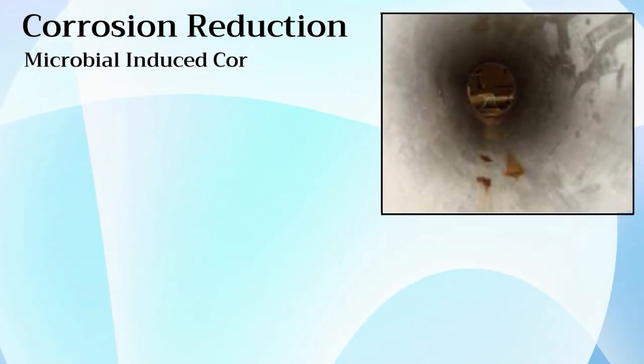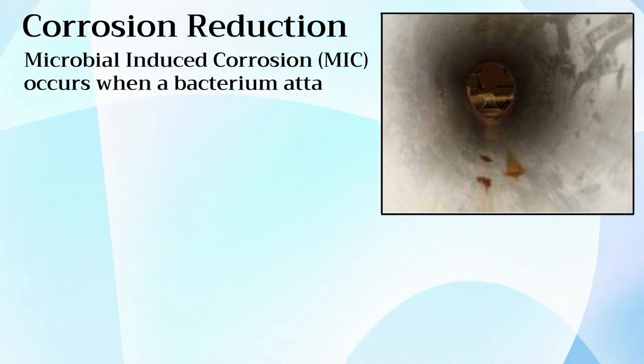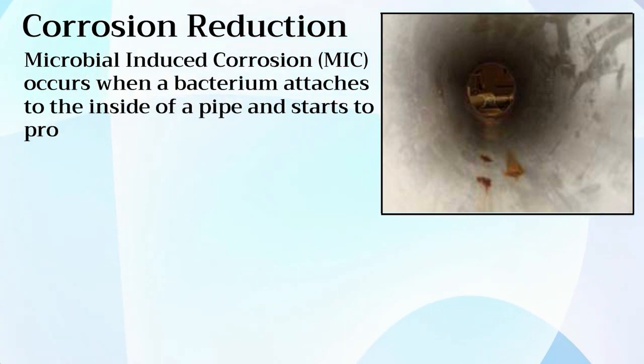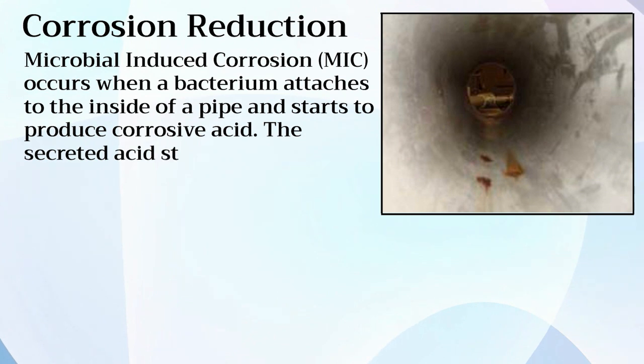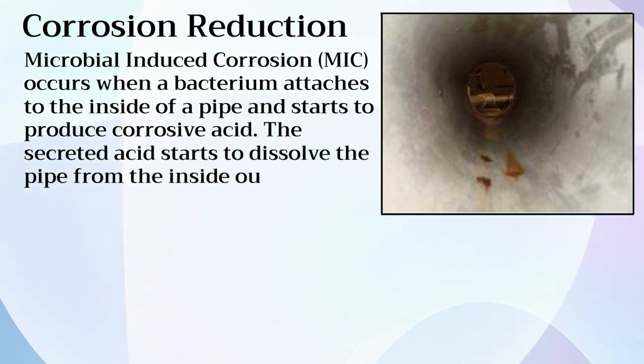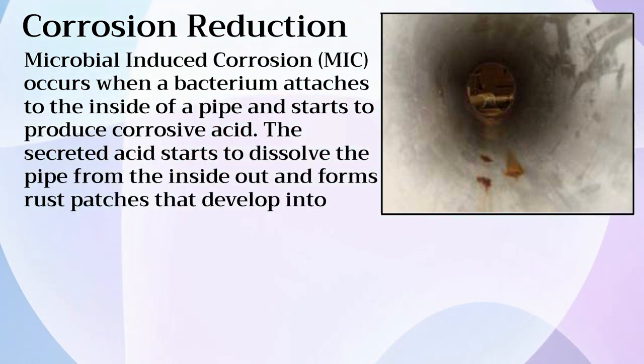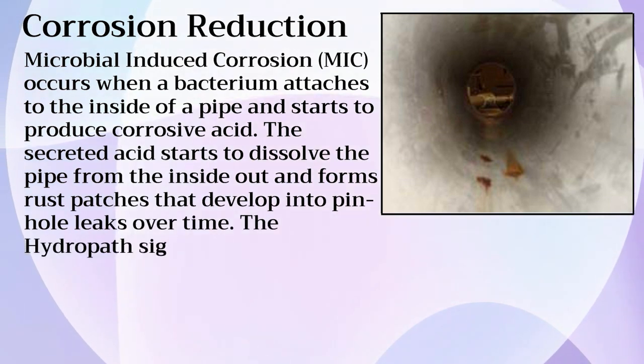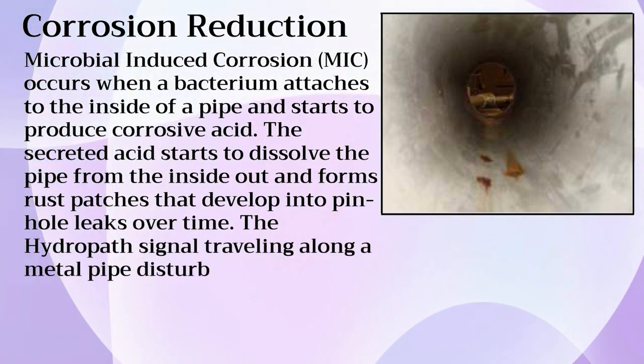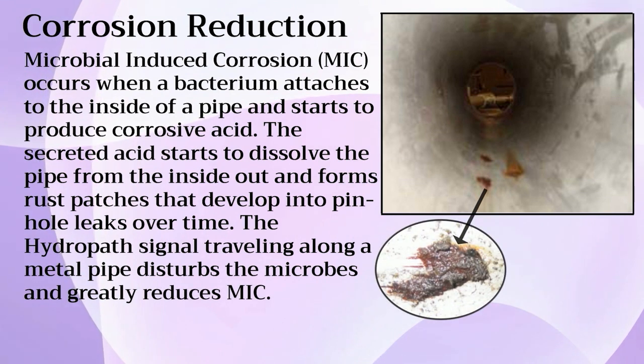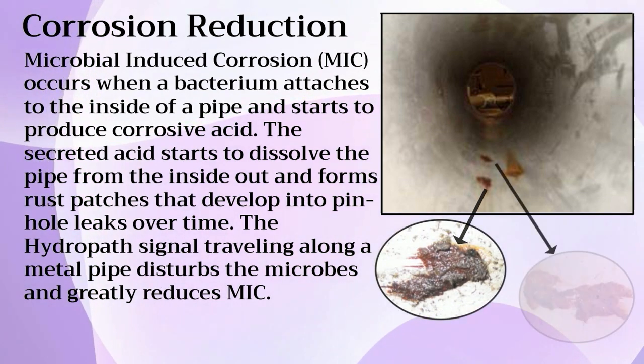Microbial-induced corrosion, or MIC, occurs when a bacterium attaches to the inside of a pipe and starts to produce corrosive acid. The secreted acid starts to dissolve the pipe from the inside out and forms rust patches that develop into pinhole leaks over time. The hydropath signal traveling along a metal pipe disturbs the microbes and greatly reduces microbial-induced corrosion.